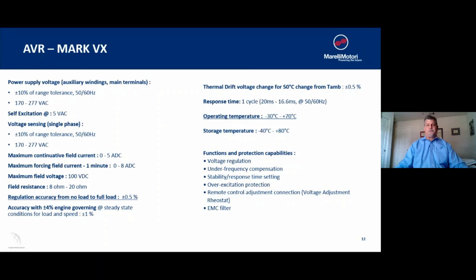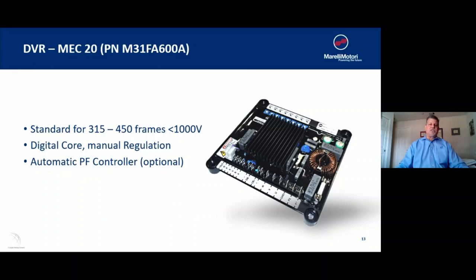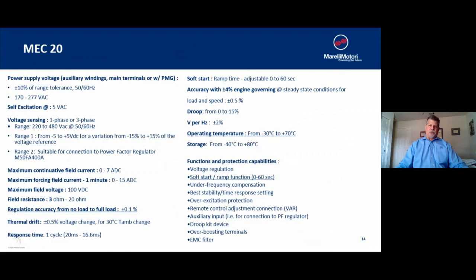Next up is the MEC 20, which has a digital core, manual regulation, and the same power factor correcting controller option. The reason it's becoming very popular even with other manufacturers' alternators is the accuracy on this one is one tenth of one percent — extremely tight windows for accuracy. It is also still good for 70 degrees C. A particularly handy feature is a soft start ramping function adjustable from zero to 60 seconds, which helps mitigate high motor loads applied to your package.